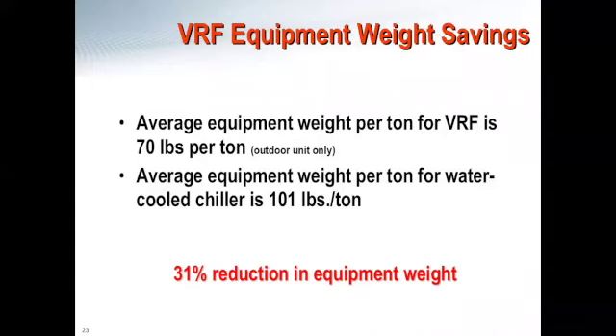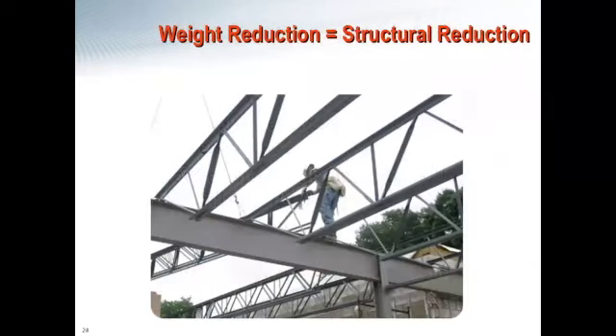This also ties a lot into VRF equipment weight savings. Your typical VRF system, on an outdoor unit basis, is going to be about 70 pounds per ton. So your 10-ton outdoor unit is going to weigh about 700 pounds. Average equipment weight on a pound-per-ton basis for a water-cooled chiller is about 101 pounds per ton. So you're going to see approximately a 31% reduction in equipment weight. While that's good in and of itself, the main difference we're going to see is the role the weight reduction plays in reducing the actual structural support needed to support the condensing units.